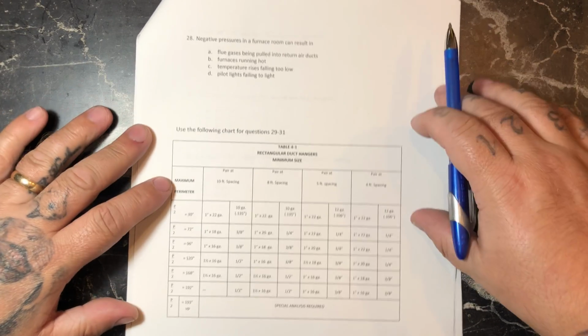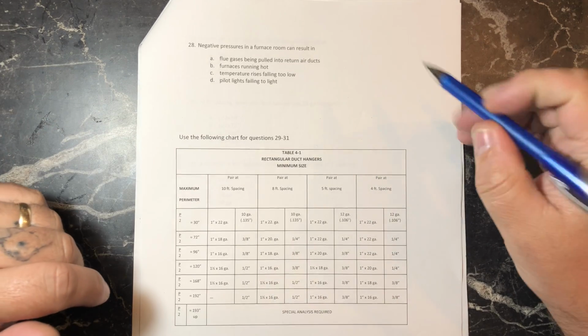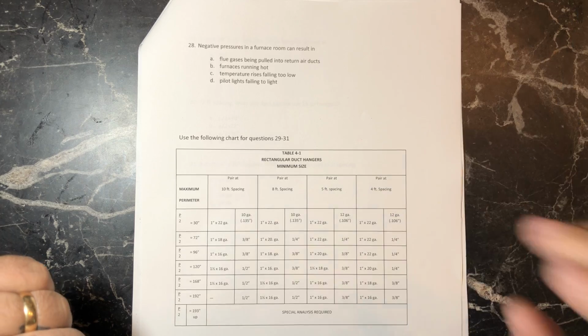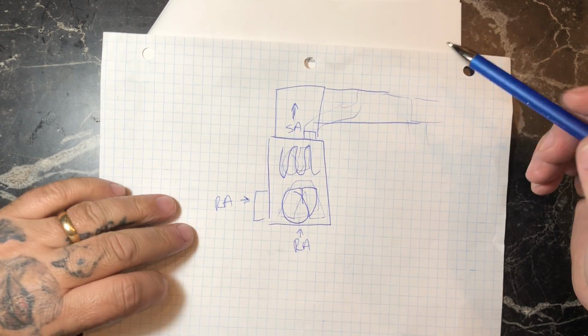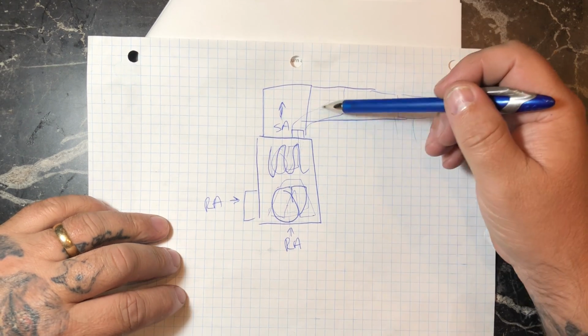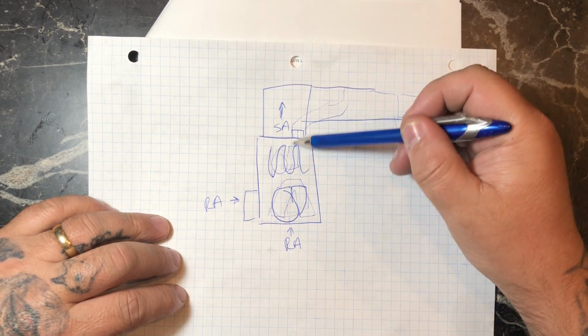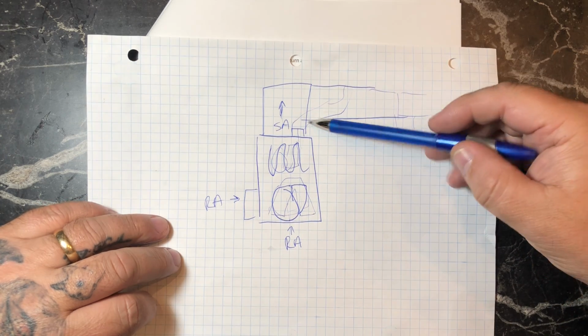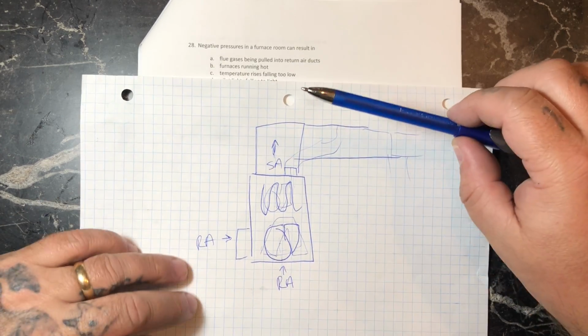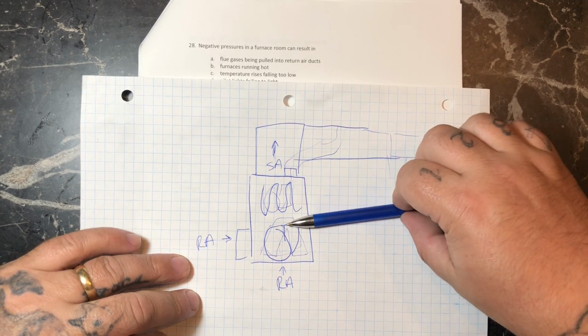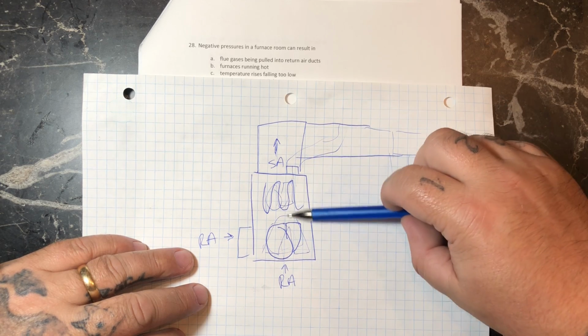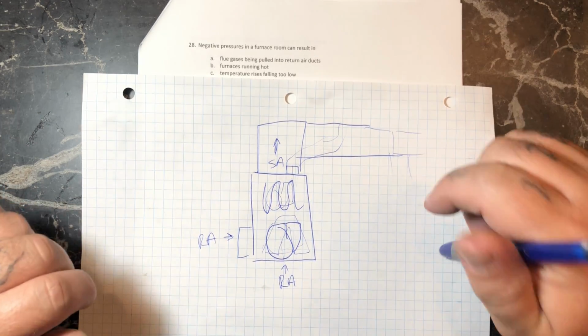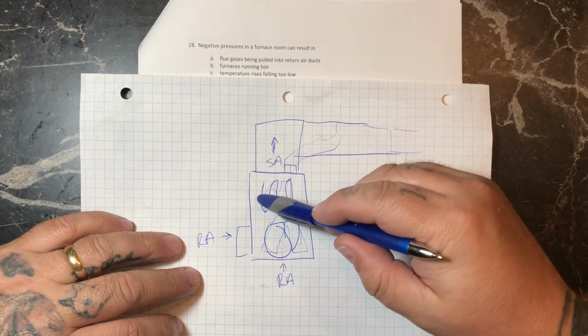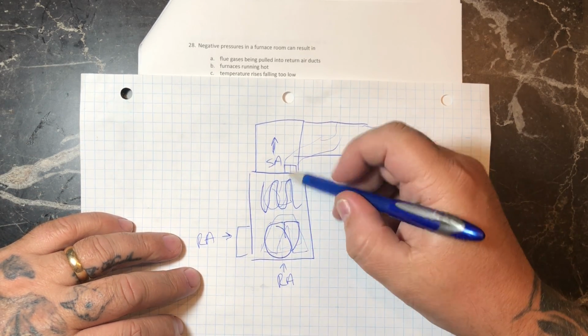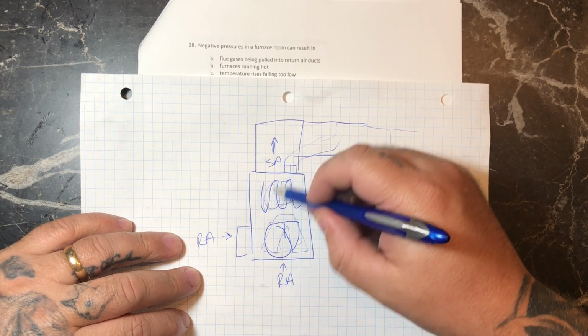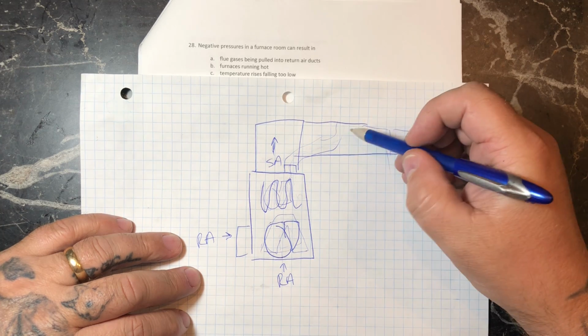Negative pressure in a furnace room can result in what? This question definitely has to do with a gas burning furnace again. So back to my picture here, which is very scribbly now. If this gas furnace has a chimney that goes up and out the building, this question has to do with old inefficient gas furnaces. An old style gas furnace would be considered a naturally aspirating appliance, which means that it has what's called air dilution. So when it's burning the fuel here, hot air rises and goes up the chimney.